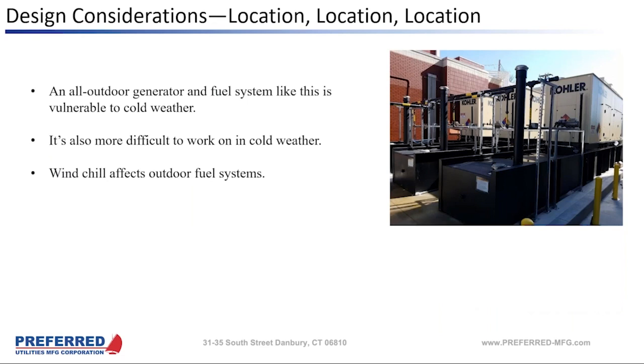So the picture here on the right is an all outdoor generator and fuel system. These are the most susceptible to cold weather. What's most susceptible is the above ground piping, especially single wall piping, because that piping is going to be up in the wind, and there is a wind chill effect when we're talking about cooling off piping, because in heavy wind you're going to transfer cold much quicker than you would if it was dead calm. So it's the above ground piping, especially the overhead piping in the wind, that's the first to gel up. Take that into consideration if you're planning on doing all outdoor gensets like this.